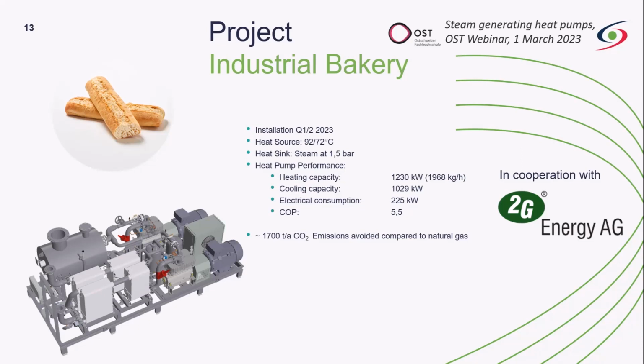Here the input temperature is a little bit higher. So we have a heat source of 92 to 72 degrees C. And we are producing really low pressure steam at 1.5 bars, which is used in this very large industrial bakery. Therefore, here the COP is quite high, with 5.5, and maybe to not extend the time.